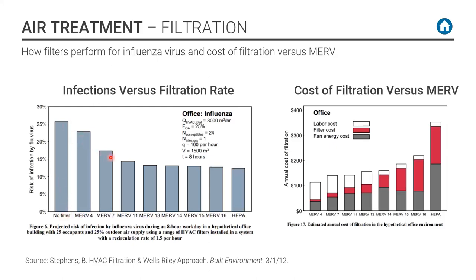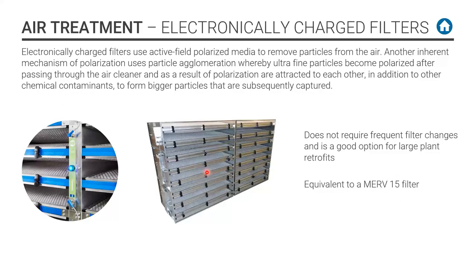And as you see, the filter gets better and better, the curve starts to flatten at a MERV 13. And at a 14 and a 15, if you notice, the risk of infectivity statistically does not go down. The reason is the 13 captures enough of the very small flu viruses, and there's really no need to go beyond this. This chart on the right talks about the cost. And as you can see, MERV 13, MERV 14 are about the same. MERV 15 is a little more expensive. And when you get into a HEPA filter, between the pressure drop and the cost, you're spending a lot more money, yet you're not getting that much of a reduction in the infectivity.